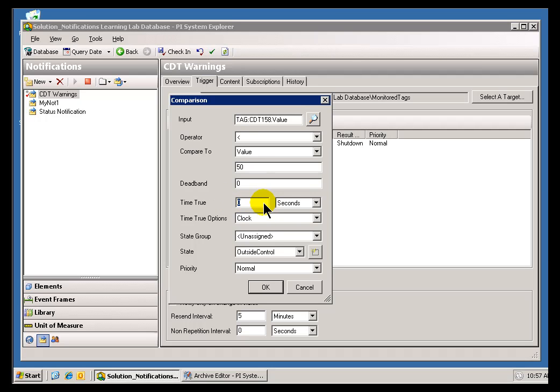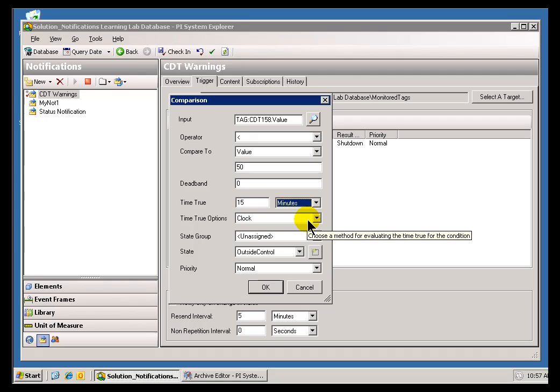One of the things we have is Time True, which is a really good reducing mechanism for Nuisance Alarms. What we're specifying here is that this condition, whatever it is, has to remain true for X number of seconds, minutes, hours, whatever. So let's say I'm only interested in this if this is the situation for 15 minutes, and then at that point we'll go ahead and send an Alarm.